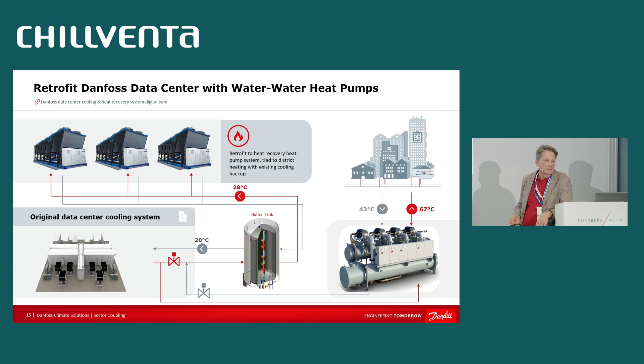The other thing we talk about is, if it is a hydronic system, it's really easy to tie in to do heat recovery, because this is the system that was implemented 3 or 4 years ago. And then 2 years ago, we implemented this. Basically what you're doing is adding a heat recovery heat pump to that existing system to preload the cooling of this same data center cooling system, based on the demand on the heating side, to supply heat to district energy. Then you're relegating the existing chillers to a backup system.